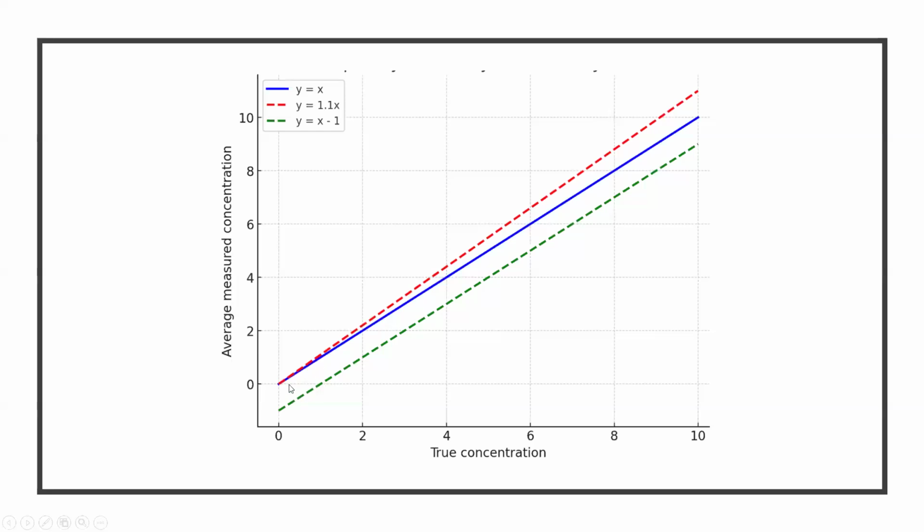If there's a bias that is the same at all concentrations, then we call that a fixed bias. So obviously the distance between the unity line and your analytical line would be fixed, and that can be estimated as the plus c term in y equals x plus c.